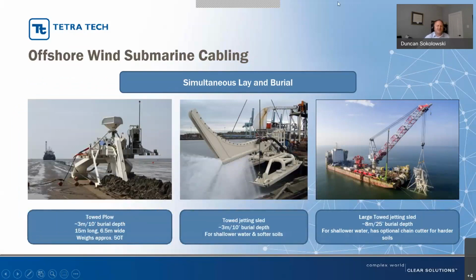So if we look at simultaneous lay and burial, here are some pictures to make it a little less word intensive. On the left we have a towed plow. These figures are a bit indicative since there are variations on a theme, but generally speaking, here we can see a towed plow in a project off the east coast of the UK, where there's a big tidal range, so they're able to place the plow on an area of seabed that dries out. We can see the cable lay vessel in the distance is also dried out, but this gives a good indication of how they work.